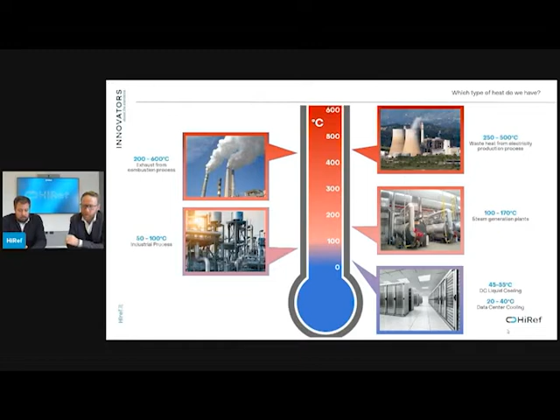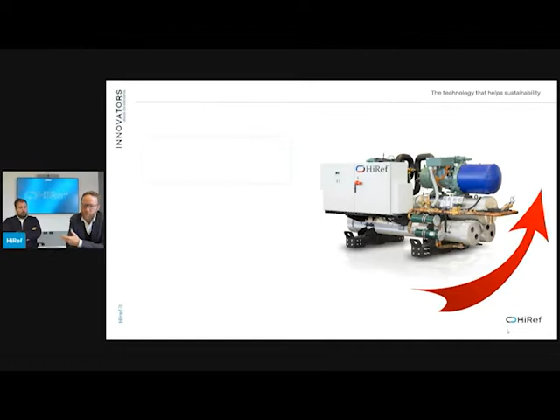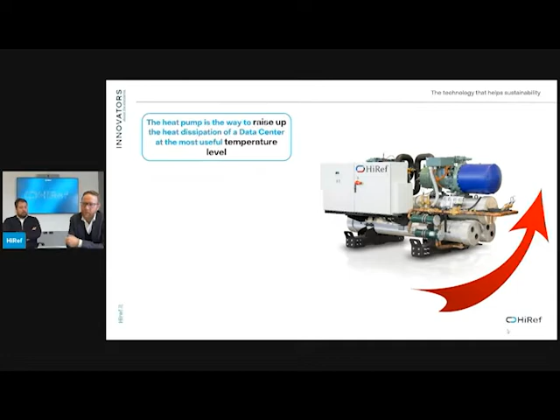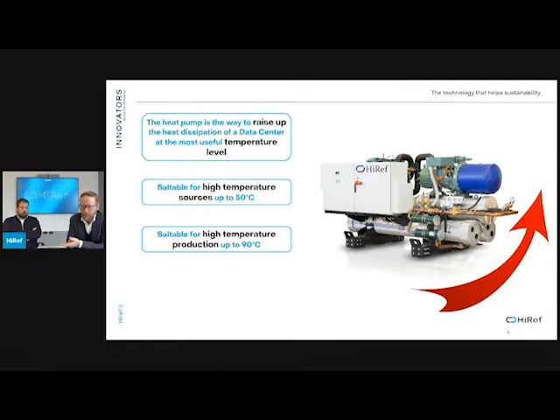It's difficult to use this kind of heat rejection in a direct way. So the best way, in our opinion, is to combine this with a heat pump. A water-to-water heat pump is the right device able to increase the temperature using as a source the data center heat rejection, which could be at 50 degrees, for example, and increase it up to 90 degrees for the combination with other applications.